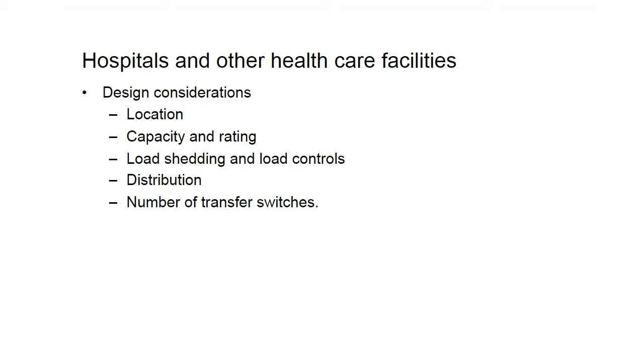So other things we want to consider when we're looking at this is the location. So you want the components of the system to be located in an area that's not going to be disrupted or impacted by natural disasters or natural forces, as Ken alluded to earlier. You want to try and maintain physical separation between different pieces of equipment. Again, if you've got a catastrophic failure of a piece of gear, it's not going to take down other components of the system. You're also going to want to look at physical separation of feeders and circuits as you distribute throughout the facility.